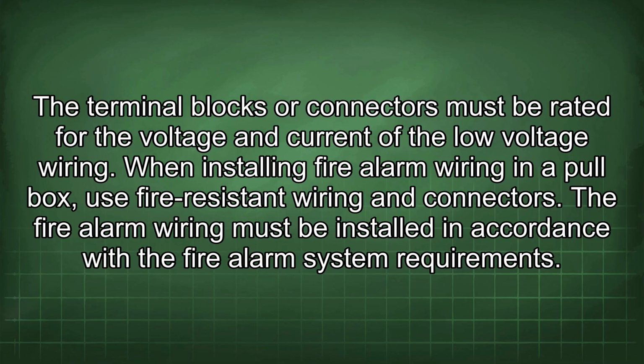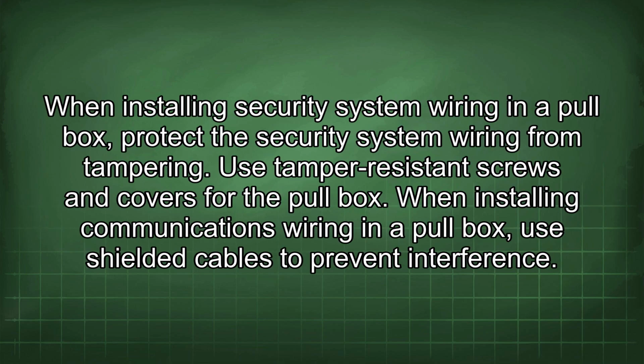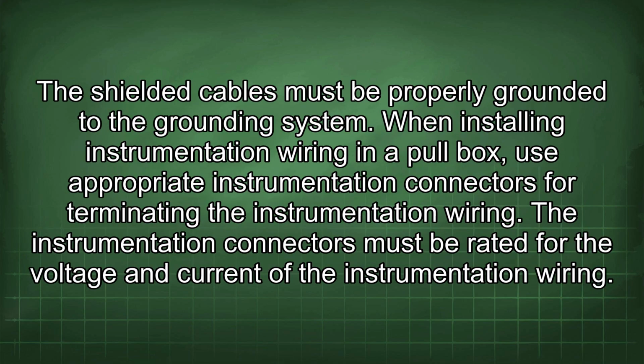When installing fire alarm wiring in a pull box, use fire-resistant wiring and connectors. The fire alarm wiring must be installed in accordance with the fire alarm system requirements. When installing security system wiring in a pull box, protect the security system wiring from tampering. Use tamper-resistant screws and covers for the pull box. When installing communications wiring in a pull box, use shielded cables to prevent interference. The shielded cables must be properly grounded to the grounding system. When installing instrumentation wiring in a pull box, use appropriate instrumentation connectors for terminating the instrumentation wiring.